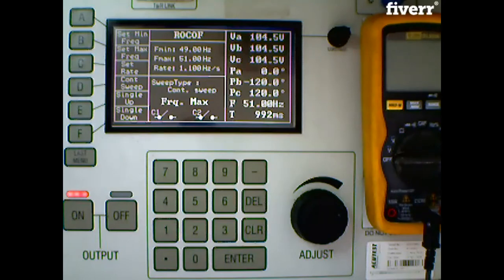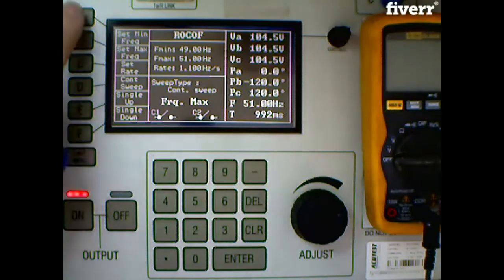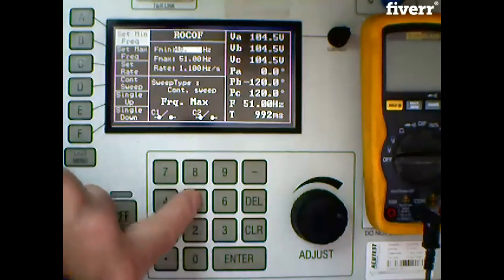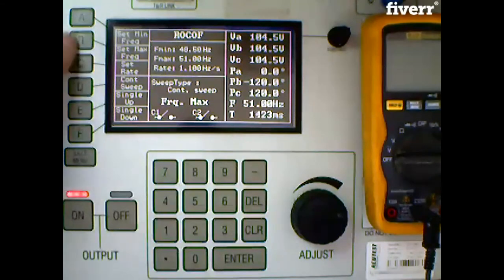Now, if we come down a section, you'll see underneath we've got a different ramp range because we've got a different setting. So we've got a down of 48.5 and an up of 51.5. So we'll change those now. So set our minimum, and we're looking for a minimum now of 48.5. 48.5, enter it.